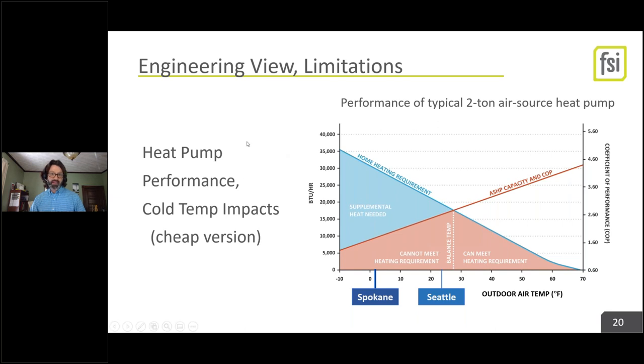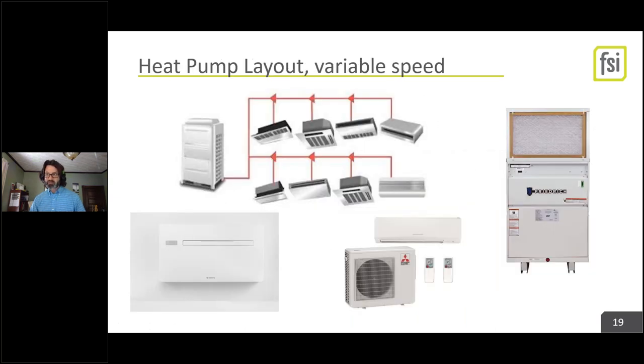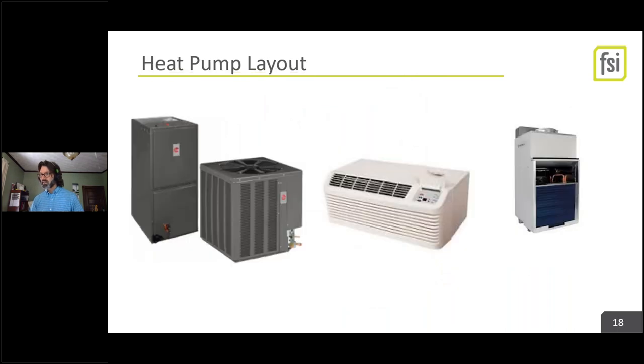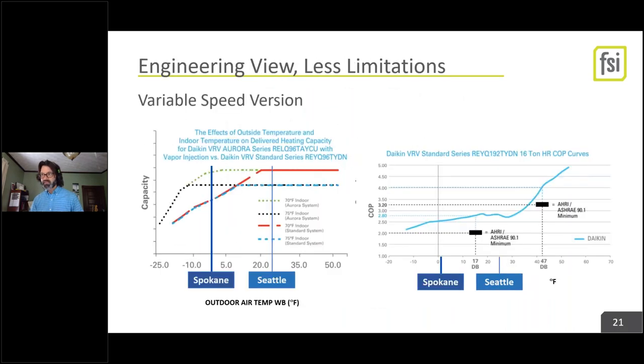So that's a VRF slide and shows the drop-off, even in Spokane, is very modest for modern VRF-based systems. VRV is a Daikin-specific thing, but it's the same thing, VRF. And if you look over on the right-hand side, the COP is still really good. It's 2.5 in Spokane at the design temp. Like, you're doing way better than electric resistance. So a lot of times, we just pick slightly larger units, planning for that drop-off at those low temps, and we don't have electric resistance at all, at least in the space heating part.